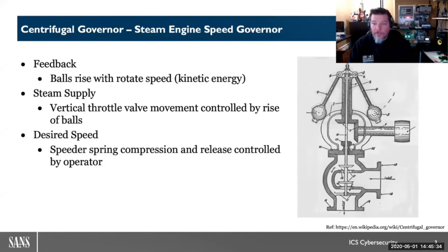This began essentially in a mechanical measures through a speed governor, as shown in the display. We have a rotating shaft — in this case directly off the steam engine. As it rotates, it spins weighted balls at the top, causing them to increase or decrease in height through centrifugal energy. As those balls increase in height, they push down on a valve controlling the steam supply into the engine. The rotation speed self-governs the amount of steam entering. The operator sets the desired speed through a speeder spring via compression or release.